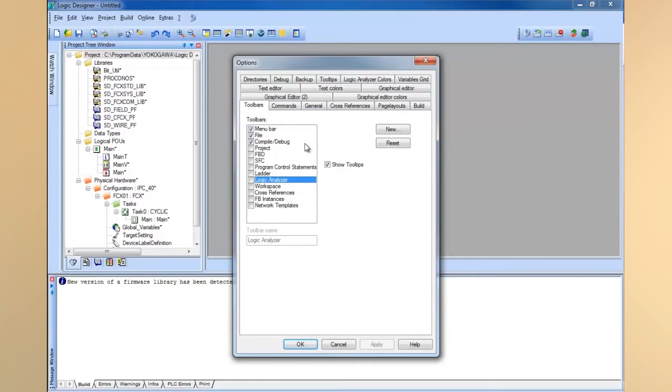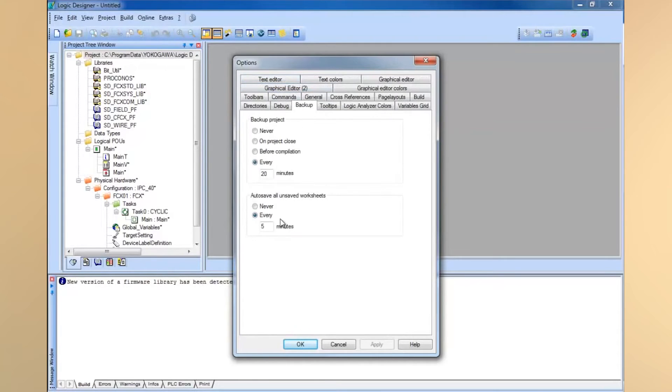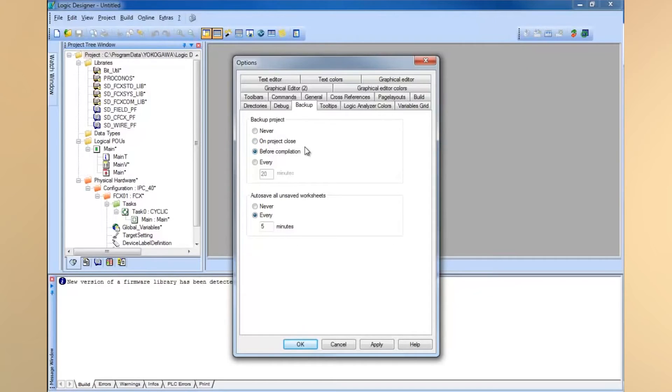Another handy thing to use is the automatic backup capability. You can select the backup tab, and something I recommend setting is before compilation. Every time you go to compile, it'll create a backup for you. You might want to just do it on project close, or periodically. But before compilation is probably a good one.